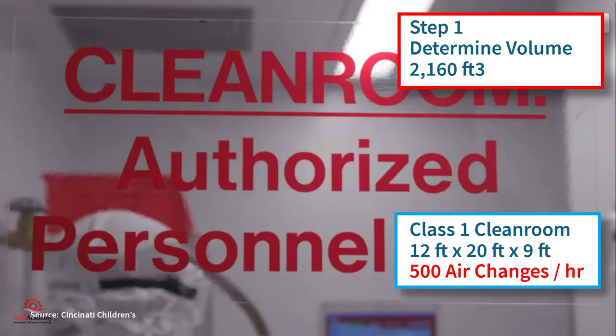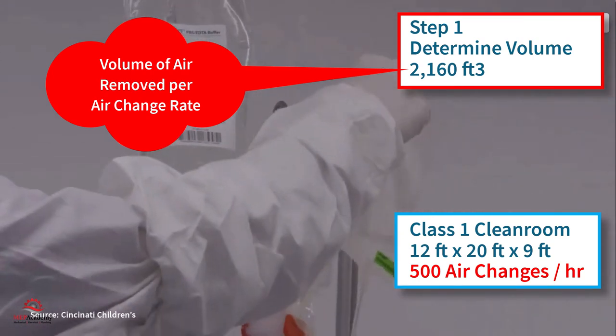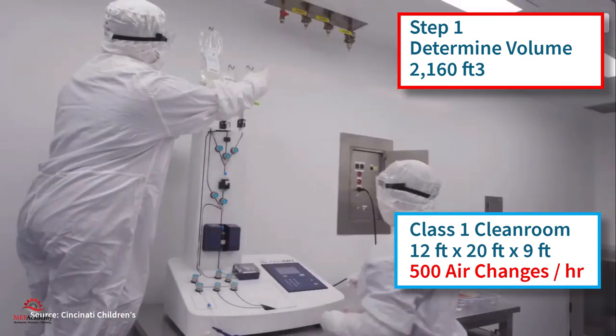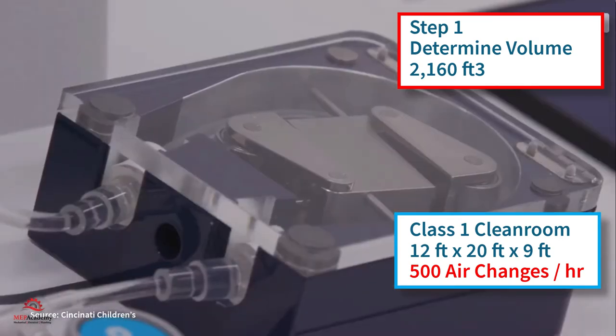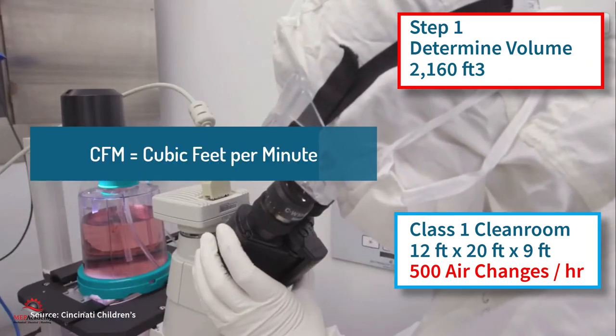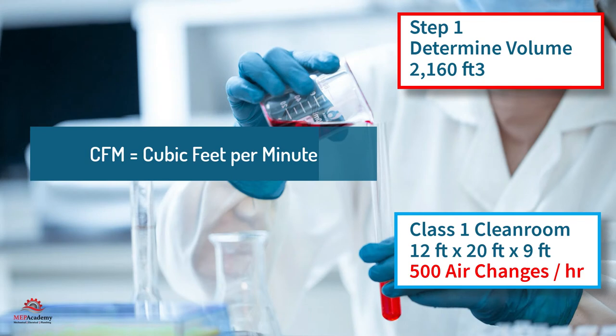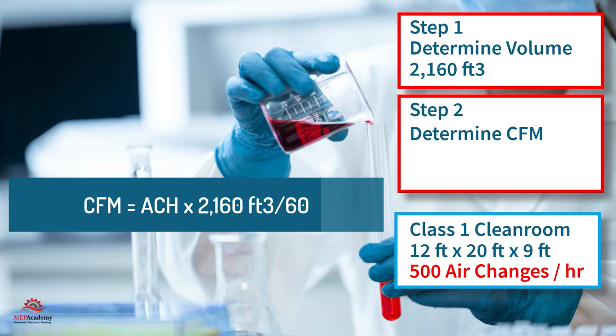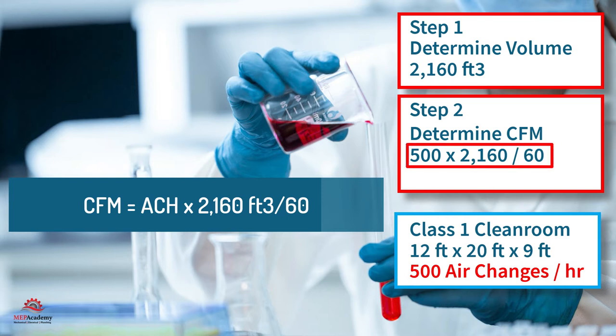This is the volume that needs to be removed from the space every hour, multiplied by the number of air changes required in an hour. This is in cubic feet per hour and we need to convert the units to minutes, as in cubic feet per minute or CFM. Step 2: determine required recirculation CFM. CFM equals 500 air changes times 2,160 cubic feet divided by 60 minutes, giving CFM equals 18,000.